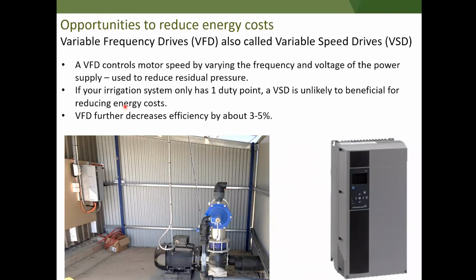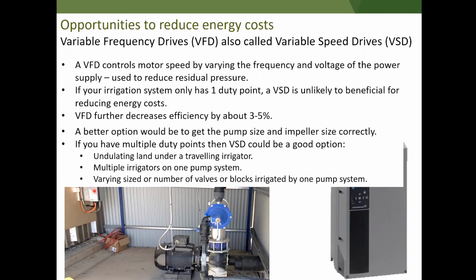The only thing is, if your system only has a single duty point, like with Andrew, it's one pivot on that pumping system, requiring one flow rate, one pressure, the VFD is unlikely to be beneficial in reducing energy costs. The VFD itself creates a little bit of extra inefficiency, so you'll actually be losing some efficiency there. But the better option, if you've only got that one duty point, is basically to make sure that the pump and the impeller are the right size in the first place. And then you don't have the outlay of that extra piece of equipment and the inefficiency through that piece of equipment.